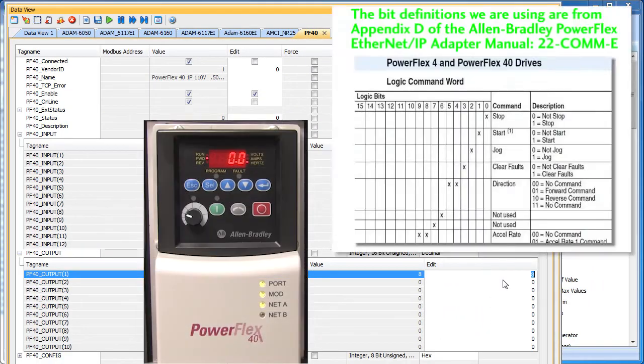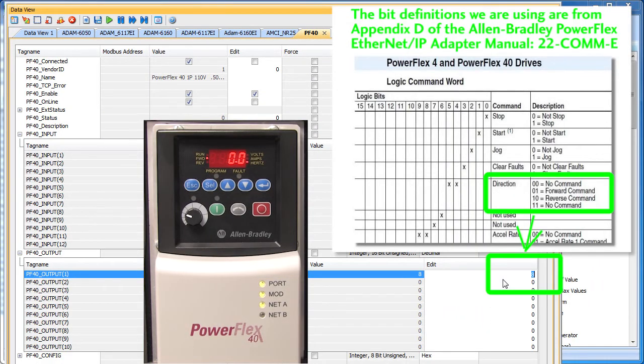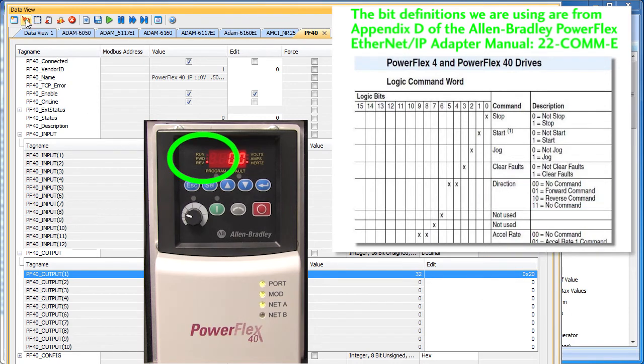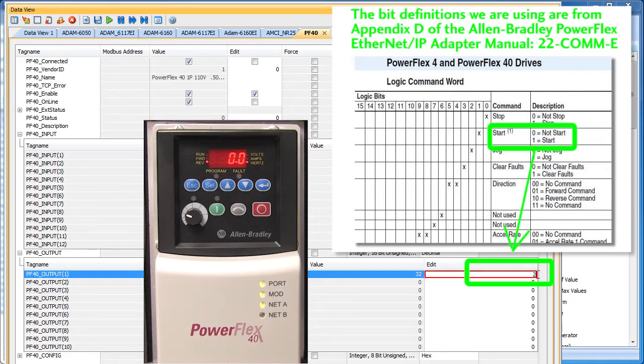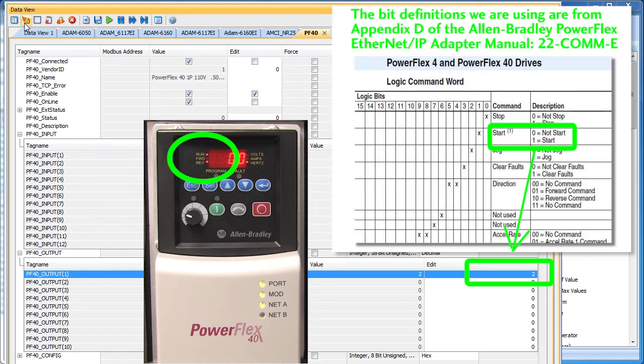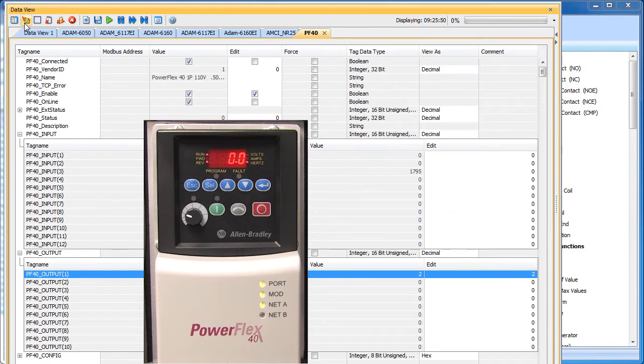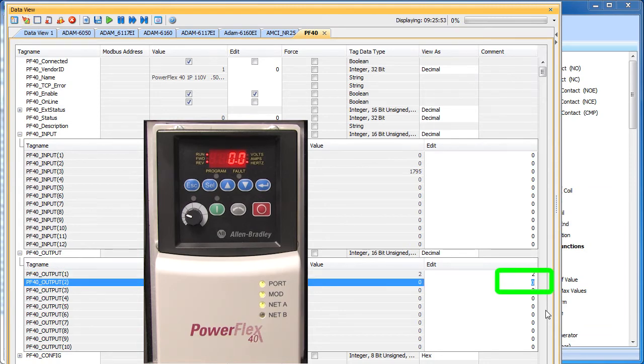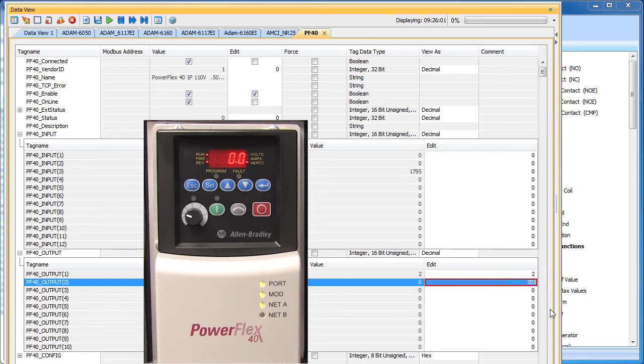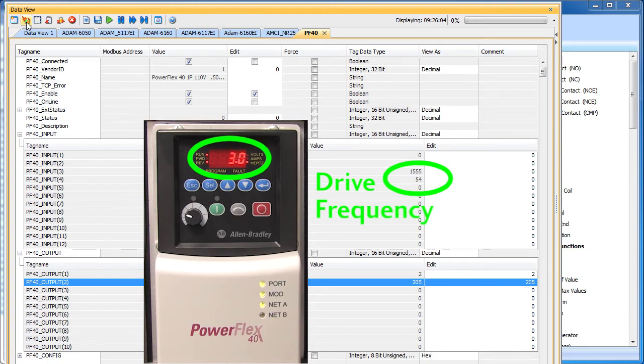Now let's just try a couple things. If I put a 20 hex in here, it should change the direction of the motor, let's try that. And sure enough it does, you can see that little LED change right on the drive. If I put a 2 in here and then write that out, the motor goes into run mode. Now I haven't specified an output frequency yet, so the drive is running, but it's not doing anything. You specify the output frequency here. Let's go to 20.5 Hz, the decimal point is implied here of course. So I write that out and sure enough the motor ramps up to the 20.5 Hz.